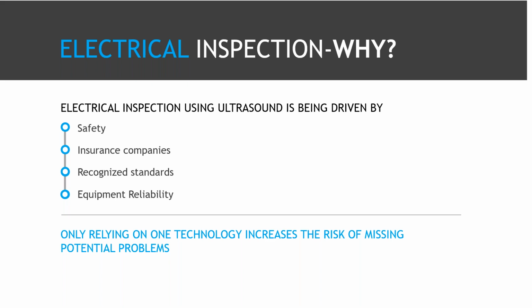So one thing we're big believers in is that only relying on one technology certainly will increase the risk of you missing something. So for those of you who have an infrared inspector coming in once a year, once a quarter, think about adding ultrasound to that. For those who are just relying on ultrasound, think about adding infrared and other inspection, visual inspections. There's all types of technology available today, and it keeps changing, and more is available. Partial discharge testing. There's all these different new technologies out there that are great for finding out if you've got problems with your assets. So we're big believers in the multi-tool toolbox.